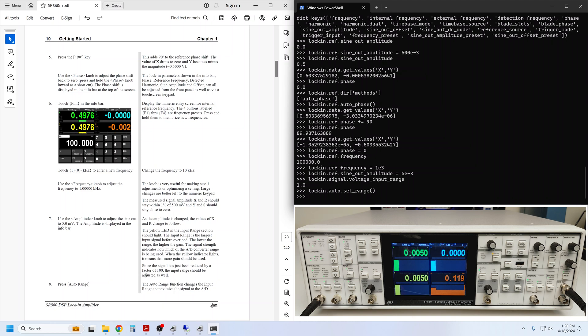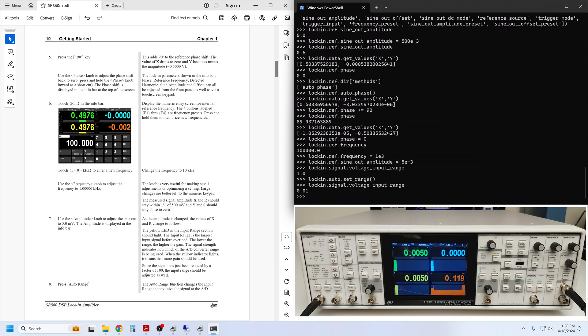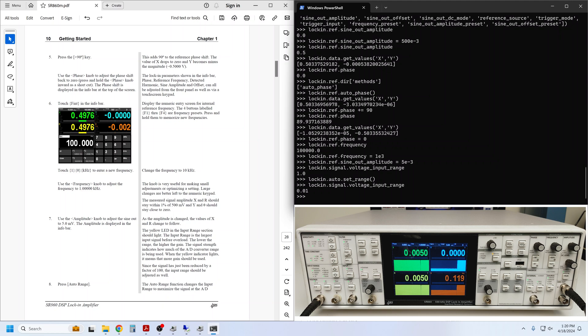We can automatically choose the best range for the present input amplitude using auto_set_range. And then we can ask the lock-in what the new input range is. The range has been reduced to 10 millivolts, the smallest range that accepts our 5 millivolt input without an overload. Actually this is the smallest range available on the instrument, corresponding to the largest front-end gain.